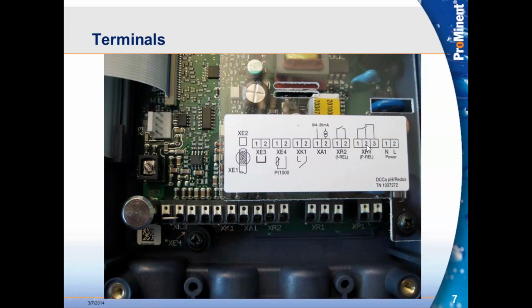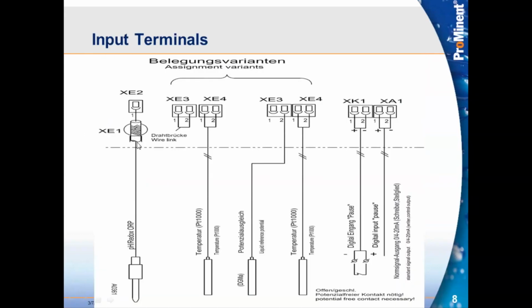it's defaulted to. But you know that we can change that, as I mentioned, to either limit or solenoid actuator. And then our input for the power to the far right. So the terminals are labeled pretty nicely, pretty clearly, I think. It's pretty simple, pretty straightforward for programming, for knowing the inputs and the outputs. So as I mentioned, the glass sensor, whether it be pH or ORP, is connected to the clamp and the terminal in front of it.